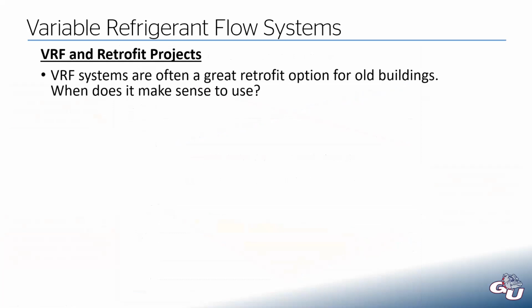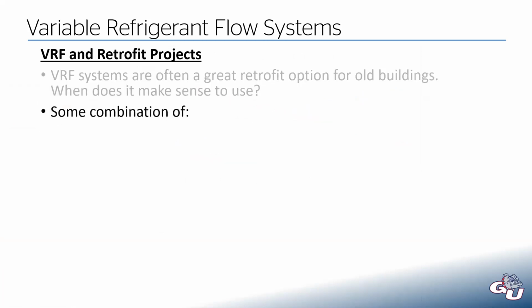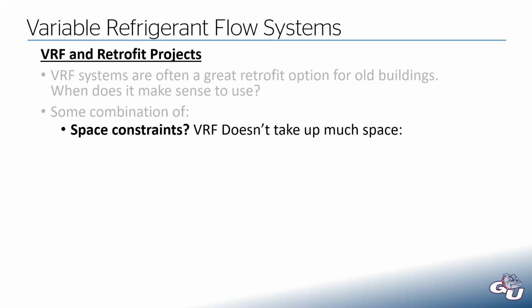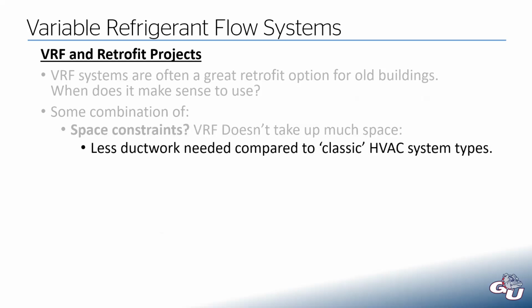I mentioned early on that VRF is really good for retrofitting existing buildings. So when would it make sense to put in a new VRF system? There are a number of things that could be true. So it's going to be some combination of the following. If you have tight space constraints, VRF doesn't take a lot of space. There's less ductwork needed compared to classic HVAC system types. That's because our fan coils are in the spaces themselves, and then the ventilation air that would have to be provided separately, because it's ventilation air only, would require smaller ductwork. And so a VRF system would take less ductwork and ultimately less space.